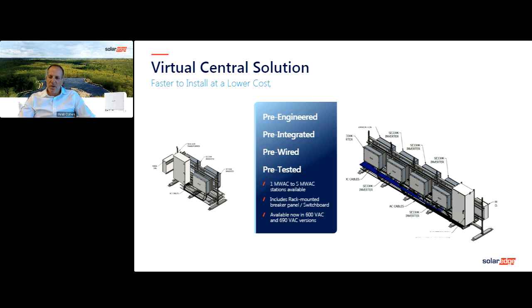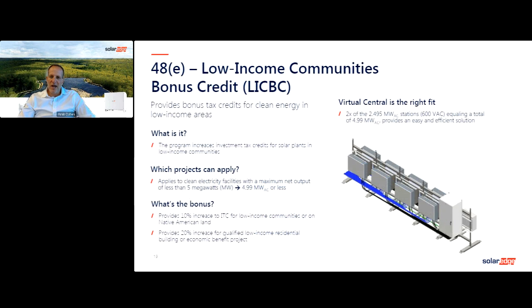Now, the nice thing is if you're doing community solar and trying to stay under that 4.99 megawatt AC requirement, 2 of these will take you to 4.99. A lot of times our competitors, if they have a building block of 250, let's say you're at 4.75 - you're sacrificing a few percentage points, and everything matters in our designs these days. So we can get you to 4.99 by deploying 2 of these skids, and that's what we did on this project.